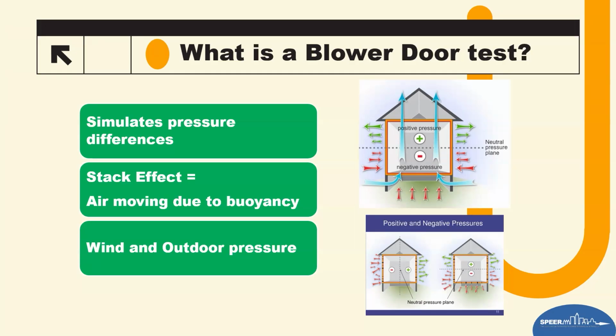Sometimes you'll hear that from windows or doors whistling. It depends on how strong the air is moving around the building to create a negative pressure. So those pressures move the air in and out of the building through all the holes in the envelope. That's what our blower door is trying to simulate, so that we can prove that things either are meeting the baseline threshold that we need for ACH or CFM per conditioned enclosure area, or they need to be fixed.